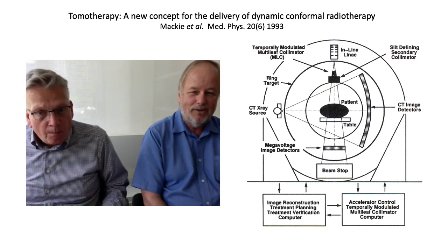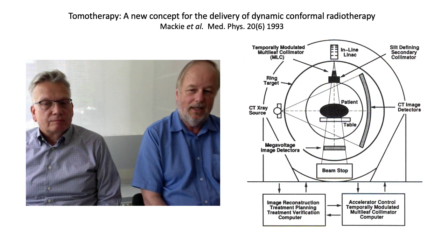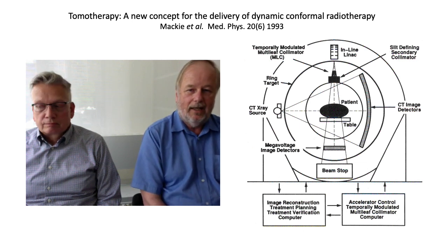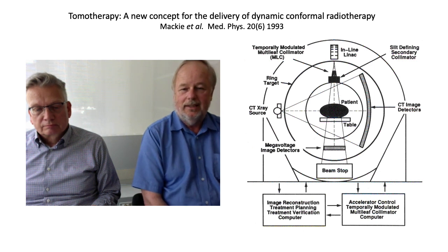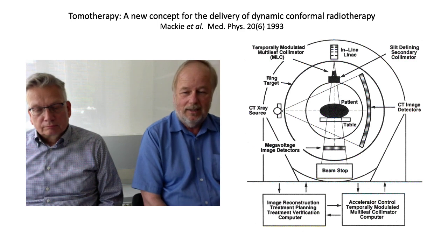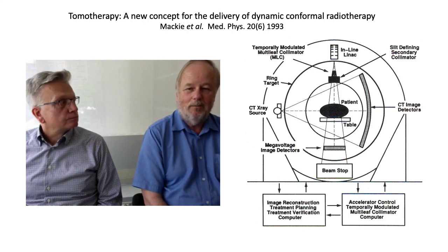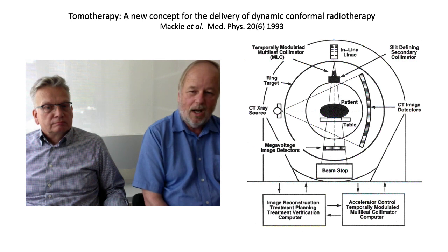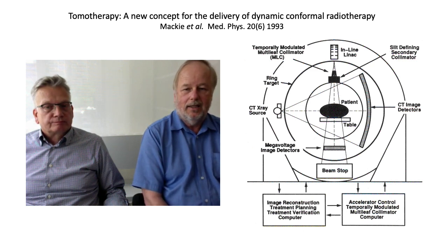The next paper is about tomotherapy, which is dear to my heart — I'm the first author of this paper. It described the first intensity-modulated radiotherapy IGRT machine dedicated to IMRT and IGRT. As you can see, it had a binary MLC and a CT x-ray source at 90 degrees to the treatment beam. The vision was to do IGRT with a kilovoltage CT-like beam. It was never actually implemented in tomotherapy because it was another piece of apparatus that would have provided excellent images, but it turned out the megavoltage image detector was probably good enough for setup verification, while not typically good enough for doing a planning study of a patient. It also showed an innovative ring target — so if you're moving around, you're not going to overheat the target.